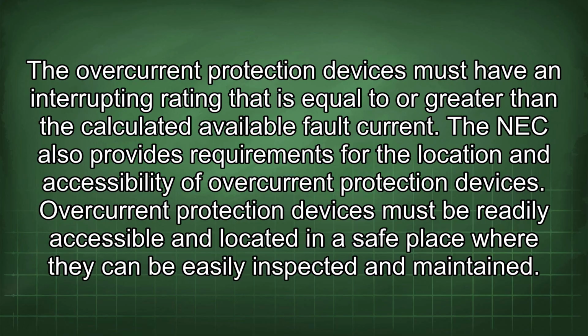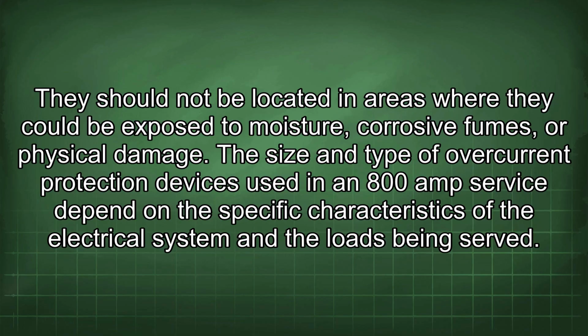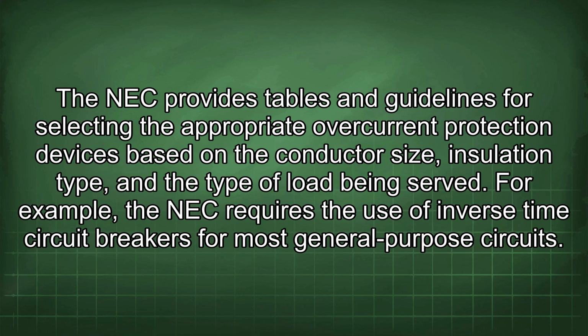Overcurrent protection devices must be readily accessible and located in a safe place where they can be easily inspected and maintained. They should not be located in areas where they could be exposed to moisture, corrosive fumes, or physical damage. The size and type of overcurrent protection devices used in an 800 amp service depend on the specific characteristics of the electrical system and the loads being served. The NEC provides tables and guidelines for selecting the appropriate overcurrent protection devices based on the conductor size, insulation type, and the type of load being served. For example, the NEC requires the use of inverse time circuit breakers for most general purpose circuits.